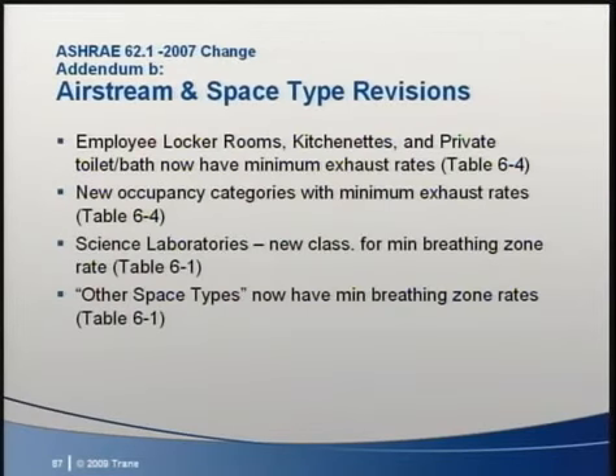Table 5.2, Other Space Types, was deleted in its entirety. Employee locker rooms, kitchenettes, and private toilet bath space types were moved from the previous Other Space Types table to Table 6.4, Minimum Exhaust Rates, as occupancy categories. Addendum B modifies Table 6.4 by designating air classifications for auto repair rooms, arena, and science lab classrooms, which is renamed Educational Science Laboratories. A classification for science laboratories was added to the minimum ventilation breathing zone rate table, along with ventilation rates now being provided for spaces that were previously classified as other space types.